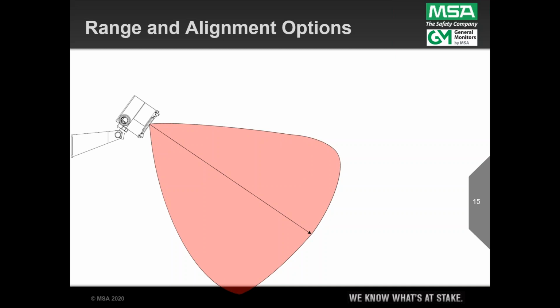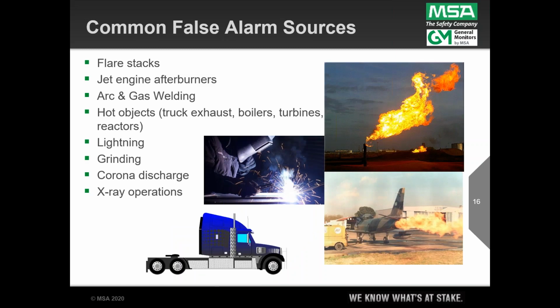And even if it's indoors, maybe in the wintertime when everything's closed, it's not a problem. But in the summer, the doors get left open, the windows get left open, and now our detector is looking out the window to next door where they've got a campfire or some crazy thing like that. In fact, talking about false alarm sources, let's talk about that. What are the most common ones for these flame detectors? Well, in the oil and gas industry, especially in places like Alaska and West Texas, flare stacks are just out there.